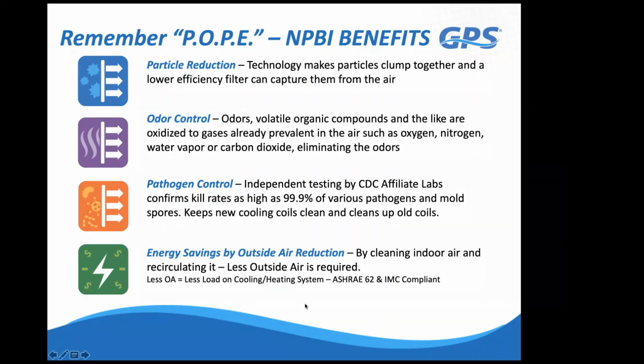If you want to get energy savings and it's not a healthcare application, we can talk about outside air reduction using the indoor air quality procedure. You also get energy savings through coil cleaning and keeping the heat transfer efficiency high, as well as pressure drop low. And the third way we get energy savings would be by using this instead of using carbon, because of the pressure drop and the final filters associated with carbon type systems.